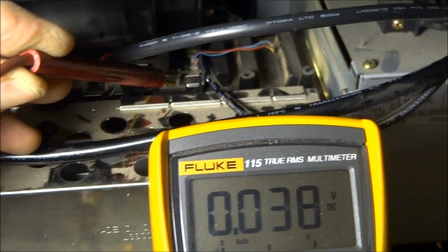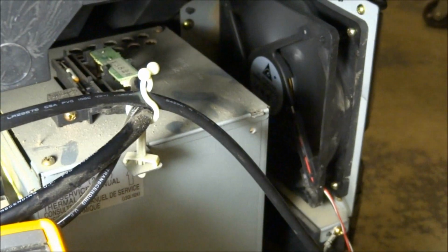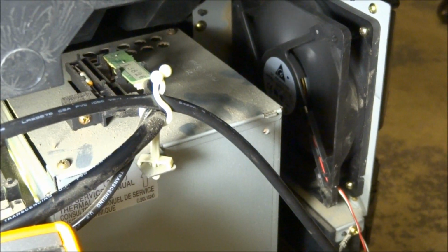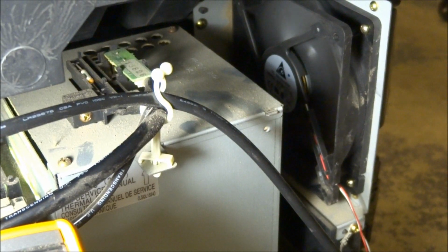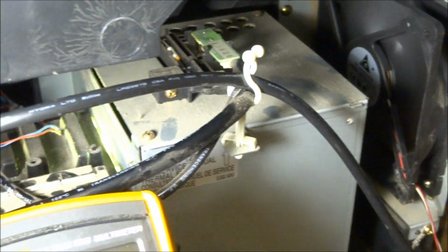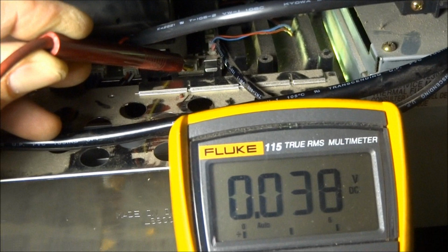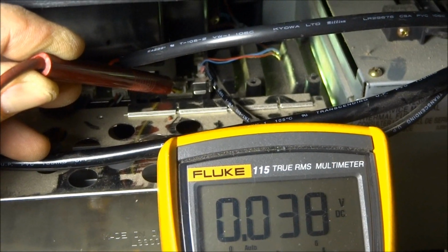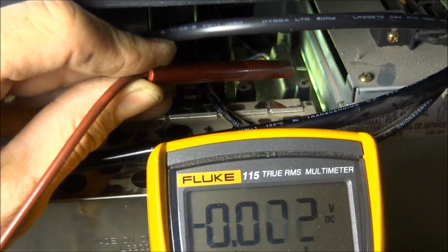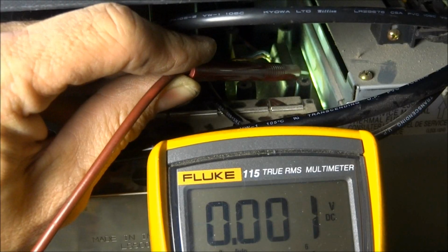You can see on this one I didn't have the exact fan we had on the last one. This is a little different, but it is a 3-lead fan with a rotation sensor, and that's the key on a set like this—to have the rotation sensor. So you can see the lamp is lit, and you can see the light leaking out right there.